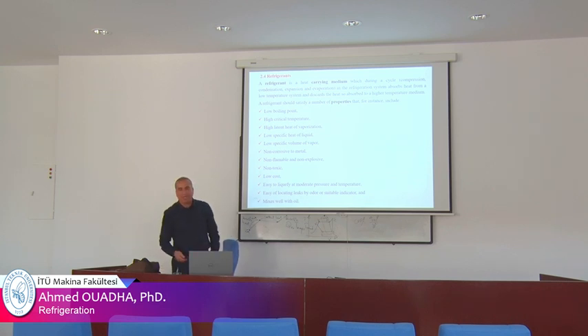Another criterion, low specific heat of liquid, Cp of liquid, it should be low. A low volume of vapor, here at 0.1, because it conditions the size of the compressor. Non-corrosive to metal: the refrigerant will be in contact with the materials that compose the system, so it should be non-corrosive to metal, non-flammable and non-explosive. This is the disadvantage of hydrocarbons and ammonia. They are explosive, and ammonia is toxic. Non-toxic is a criterion; ammonia is toxic, but it is present in industrial applications where there are no humans, because for applications with humans there are some norms to respect.